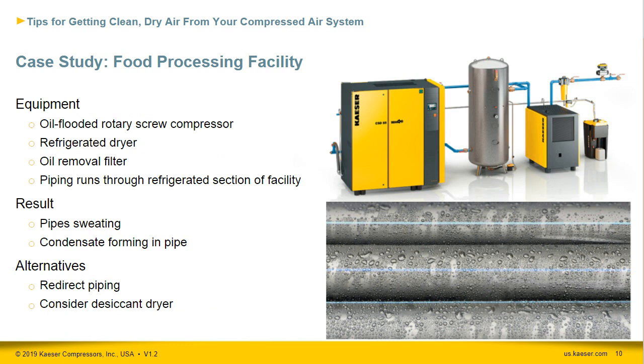Here's a good example of what we're talking about. Compressor, tank, dryer, filtration, that's what we see in the top right. That's in one area of your facility, your compressor room. The dryer was a refrigeration-type dryer. So if we go back to our ISO air quality schedule, that could be between 38 degrees Fahrenheit and 50 degrees Fahrenheit pressure dew point, depending on the type of dryer, the operating conditions, and the design. This pressure dew point level was supposedly fine for the entire facility.